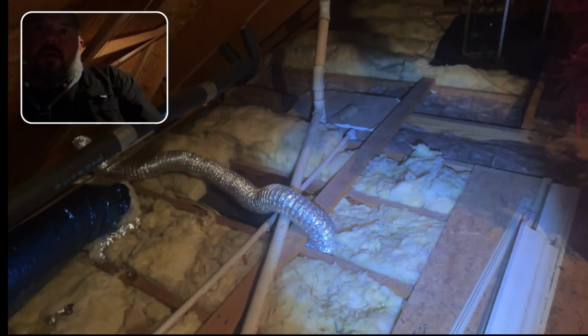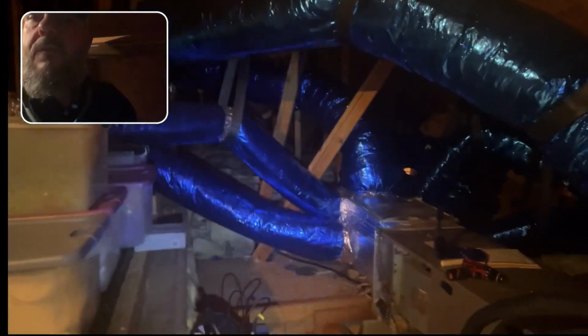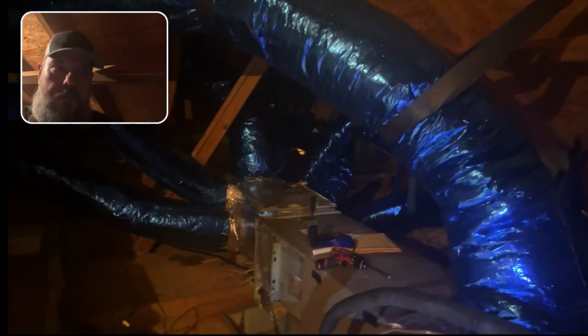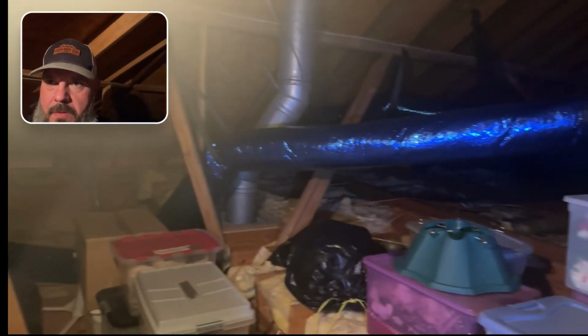This white PVC right here that's insulated is the main drain line. It has a belly in it right there where it's insulated, and then the insulation stops right there, and you can see it is full of microbial growth, water staining, and it too in fact is up pitched. I don't know if you can tell that. And then it runs all the way over there to a P-trap, which is not insulated, and it is condensating as well. So this system was recently retrofitted with new return airs, trunk line, new supply air, plenum, and all new flex ductwork. And as you can see, they had good intentions. They were well intended, but they just executed very poorly. The reason this was done was because of the suspicion of microbial growth inside the ductwork.